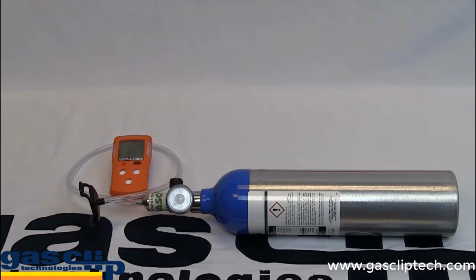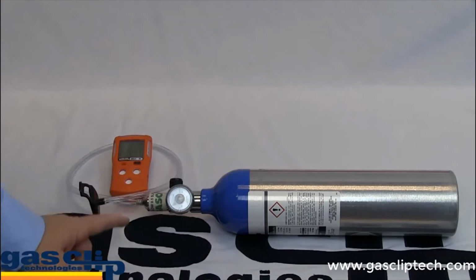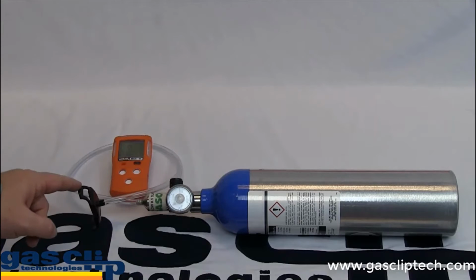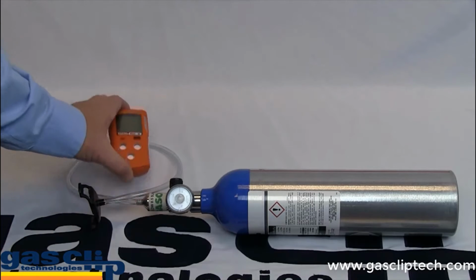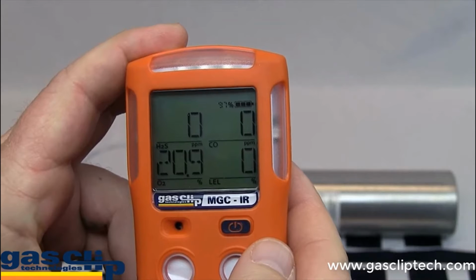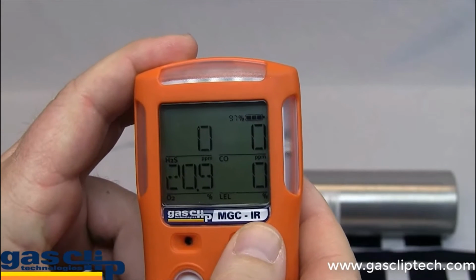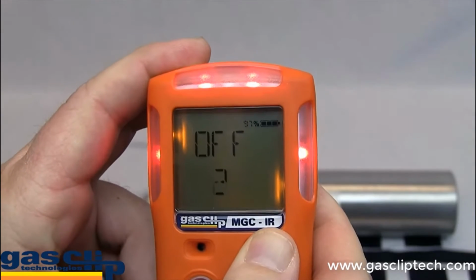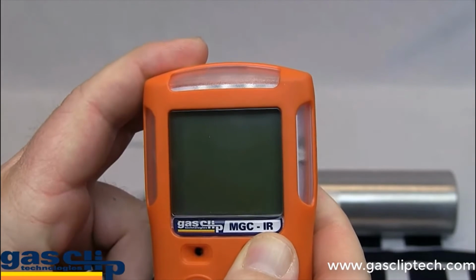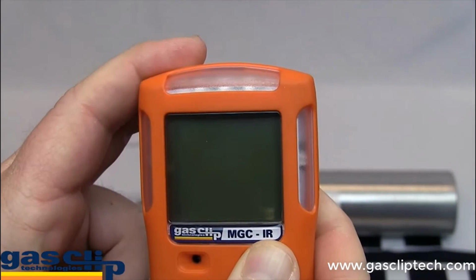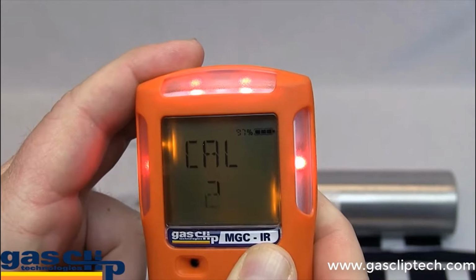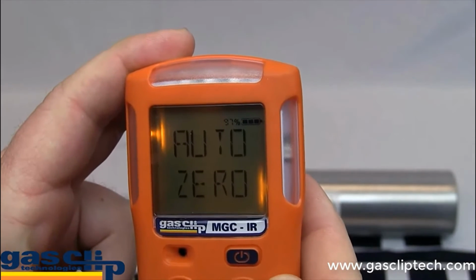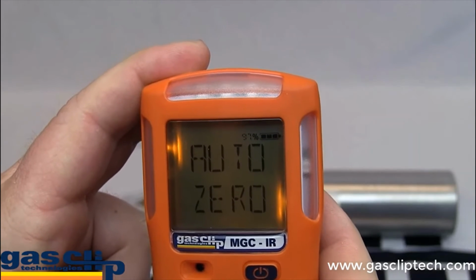The multi-gas clip can also be manually calibrated using a bottle of gas, a regulator, the provided calibration cap, and of course your monitor. To perform a manual calibration, simply press and hold the power button down. The monitor will say off 3, 2, 1. The screen will go blank. Continue holding the button. It will turn back on and say cal 3, 2, 1. Release the power button and it will soon say apply gas.